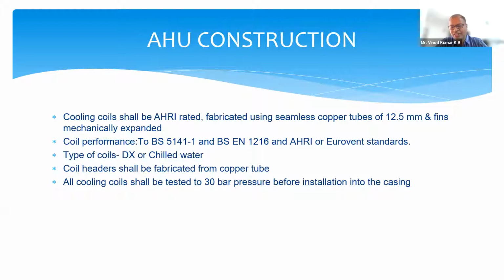Now, if the coil is wrongly sized, the copper tubes and fins are not exactly as per the requirements, it will not perform. The water or the refrigerant gas which is cool will come and go without giving its chillness to the air. Now what happens in the process? You are not going to get the correct temperature inside your space, which is the OT or the ICU. So here the specialist AHU vendor should make sure his coil performance is set to BS standards or AHRI or Eurovent standards. Okay, and very important is the coil, since it carries water or refrigerant gas, it has to be factory pressure tested before it is actually brought to your system. At the same time, you'll have to pressure test on site so that you can ensure that there is no water leakage.